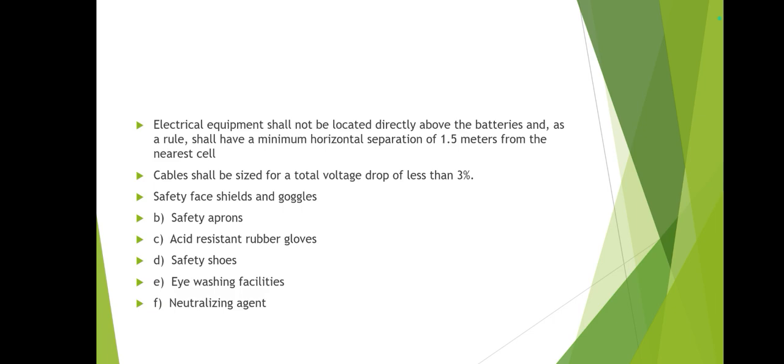Electrical equipment shall not be located directly above the batteries, and as a rule shall have a minimum horizontal separation of 1.5 meters from the nearest cell. In Aramco, no electrical equipment is allowed inside the battery room at all. However, in SABIC plants I have seen battery cells installed in the same substation area, so from the battery cell to the electrical equipment the distance shall be 1.5 meters, as permitted per NEC standard.